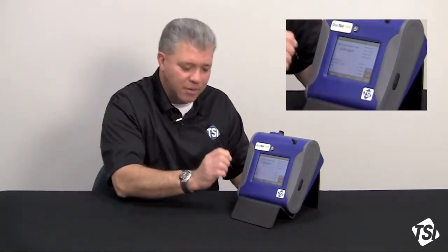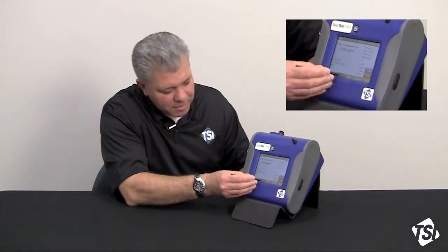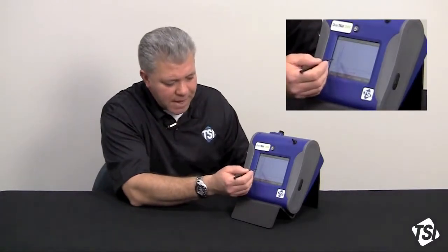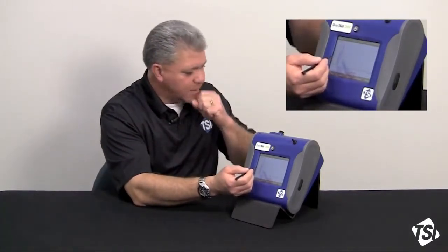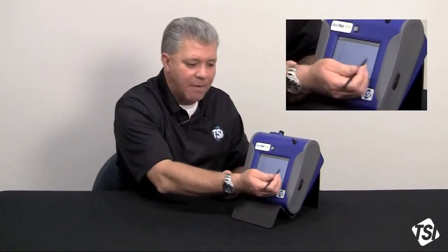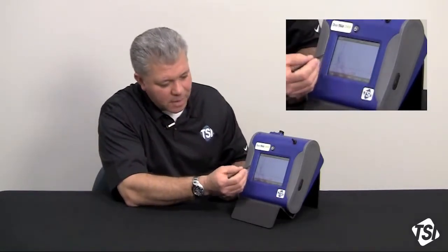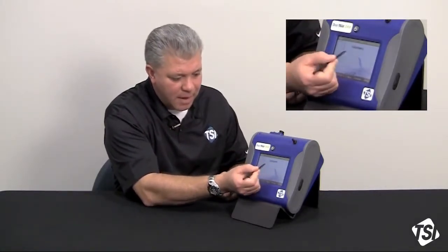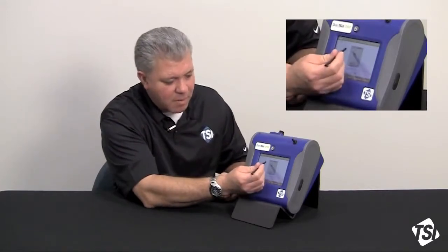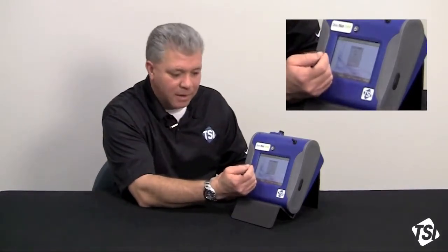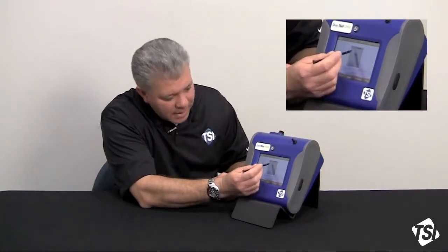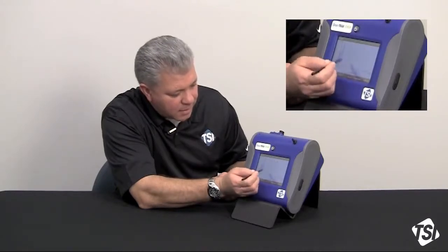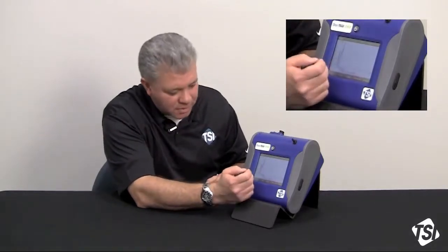Now here's an interesting thing to look at. We have the ability to look at a real-time graph of data. What you will see is a 5-minute rolling average that goes across the screen. I also have live keys here. If I go up into this area and touch in here, I can look at, do I want an average or a TWA line through my data? And I'm just going to select average. Going to highlight that. Click OK. And now I'm going to get an average concentration line.